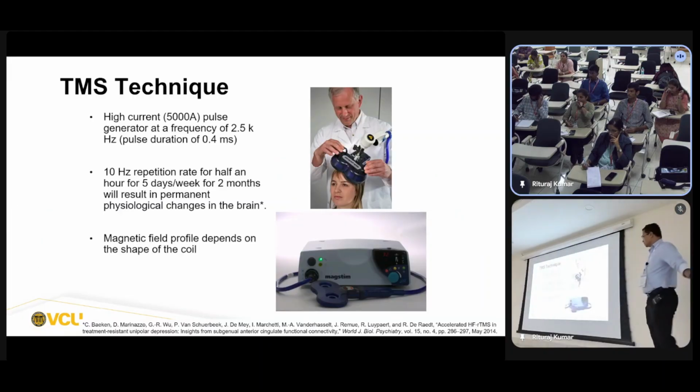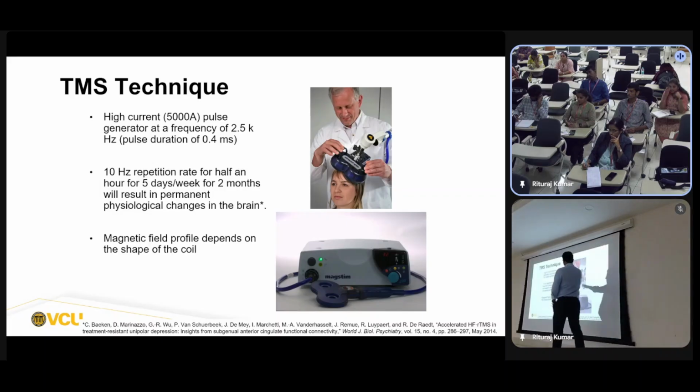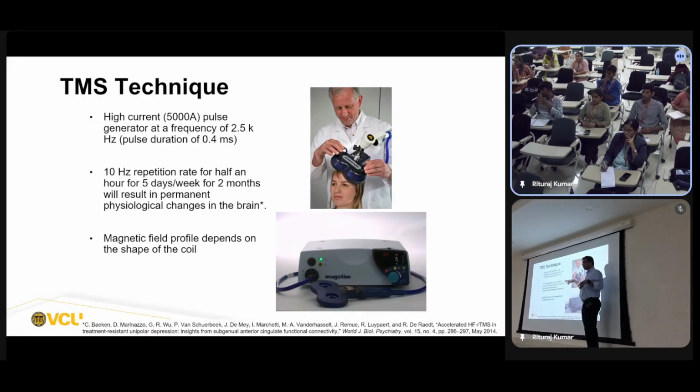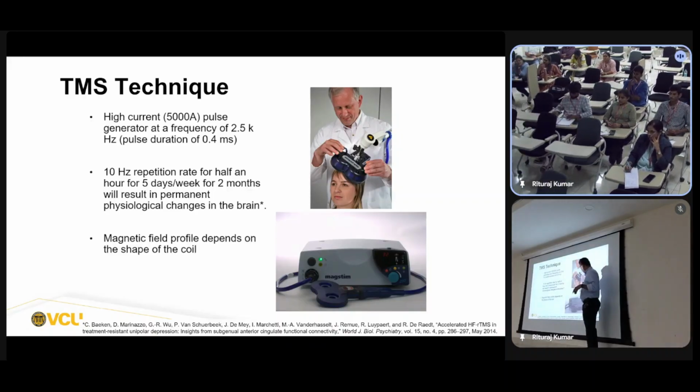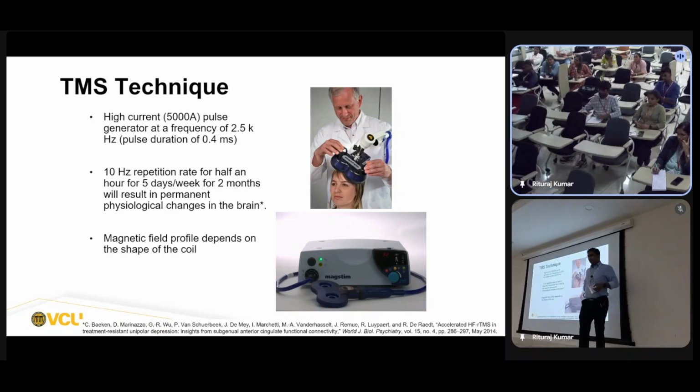That's how TMS works. And this is how a coil looks. This is just copper windings, and it's placed on somebody's head. And the coils look like this. This is used for 1 hour long stimulation because it needs to be cooled. When you do it for 1 hour or 45 minutes, it heats up a little, so you need some cooling fan here. This one is laboratory grade, so you don't need 1 hour stimulation.